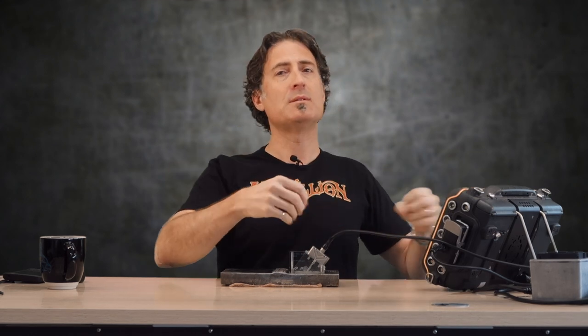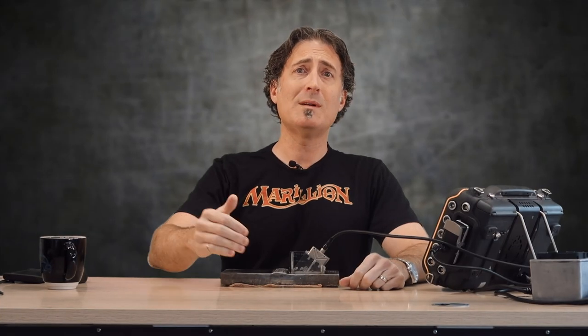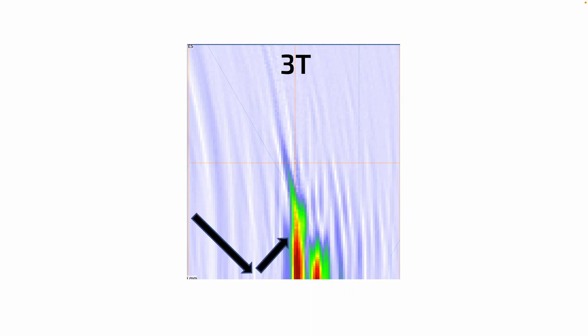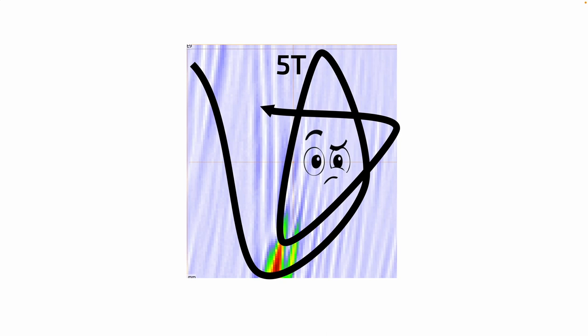Remember, when you fire the probe, you can't tell it to fire those propagation modes — it just does what it wants to do. All we're doing on the back end is reverse engineering the A-scans based on the time of flight. Let's take a look at some of the common ones. TT is transverse-transverse, so that's just shear waves — first leg inspection, kind of the top half of your S-scan. 3T is down to the bottom, up to the reflector, back to the probe, or the reverse order. 4T is a second-leg inspection, so it's kind of the bottom of the S-scan. And 5T — it's kind of hard to draw.